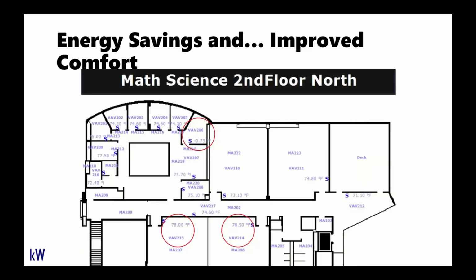So here's another example of the math and science building. Here's a few of the zone temperatures that we were looking at in the building, and you can see circled in red here that we've got some problems. There are 2 rooms here that are over 78 degrees, certainly outside of the comfort range for a typical building in this climate, and possibly even more importantly, out of certain recommended ranges by ASHRAE for occupant safety now. And then another room here was showing negative 0.7 degrees, which is obviously not correct, but indicates that that sensor is not working.